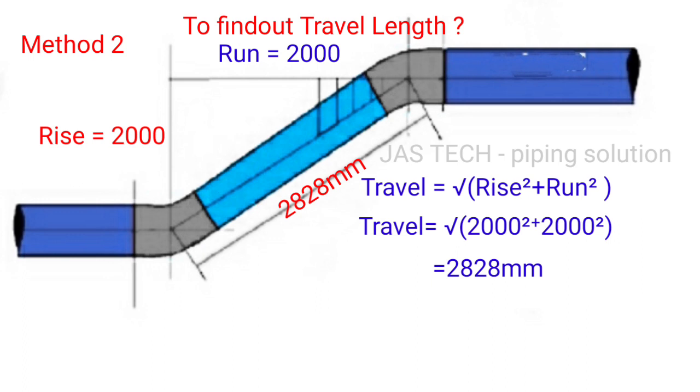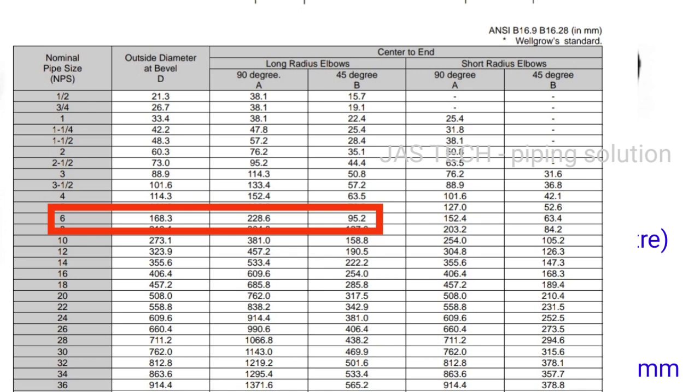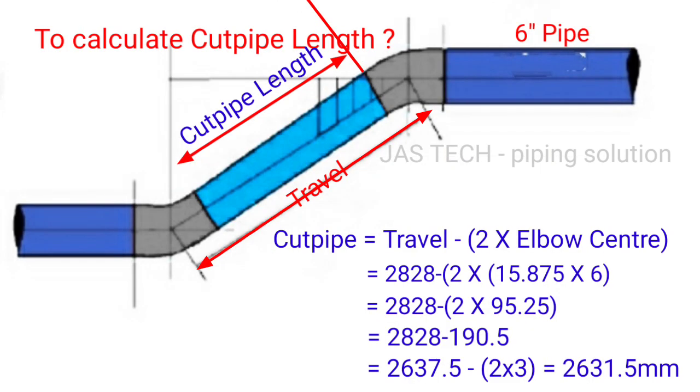Final formula to calculate cut pipe length: cut pipe length equals travel minus 2 times elbow center. Travel distance we already know is 2828 mm.